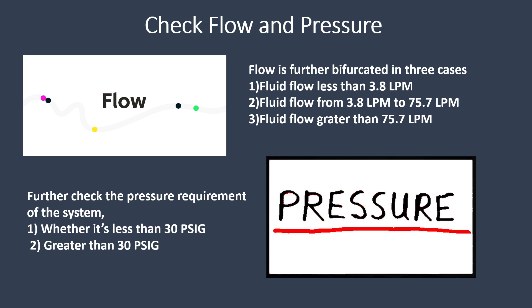First, we need to check the flow and pressure requirements of the pump. Flow is bifurcated into three cases: (1) fluid flow less than 3.8 lpm, (2) fluid flow from 3.8 lpm to 75.7 lpm, and (3) fluid flow greater than 75.7 lpm. Further, check the pressure requirement: whether it is less than 30 psig or greater than 30 psig.